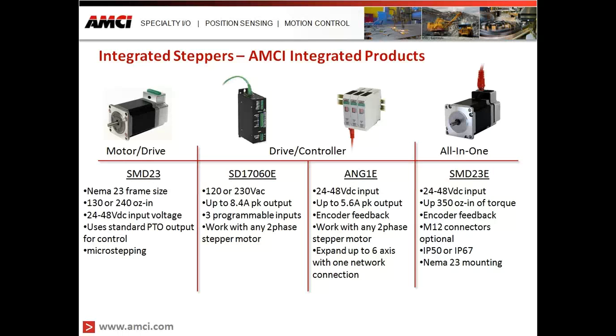Our integrated drive and control is available in either AC or DC input voltage. The AC version has a peak current output of up to 8.4 amps, and the DC version has a peak current of up to 5.6 amps. Both integrated drives work with standard two-phase stepper motors and have programmable inputs for additional functionality such as registration, electronic gearing, and homing.